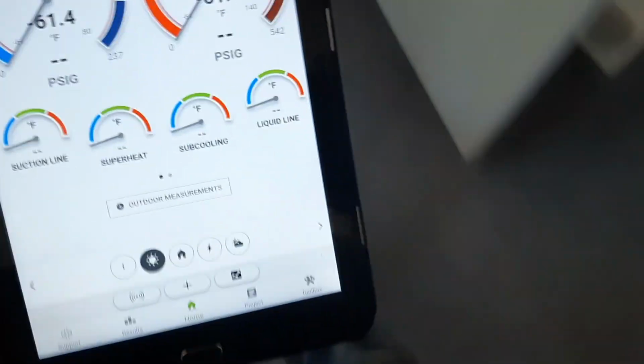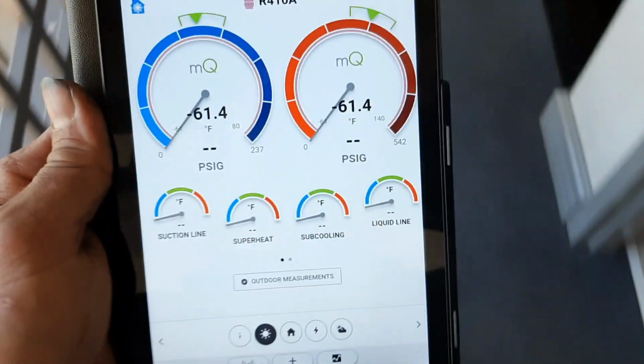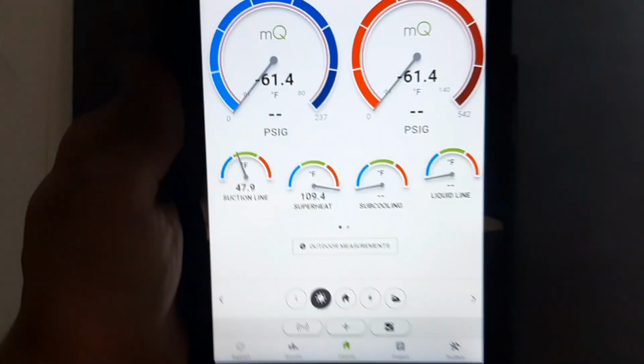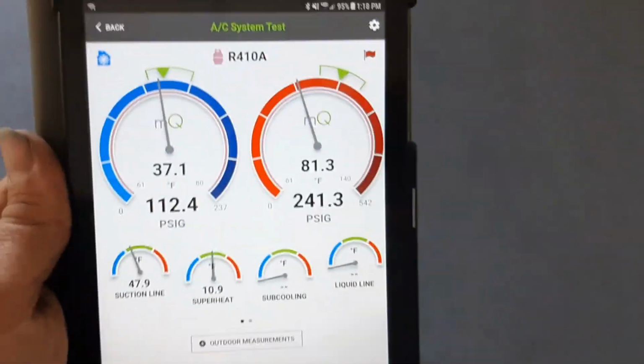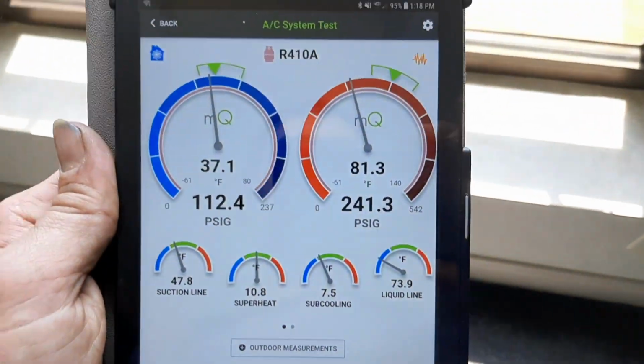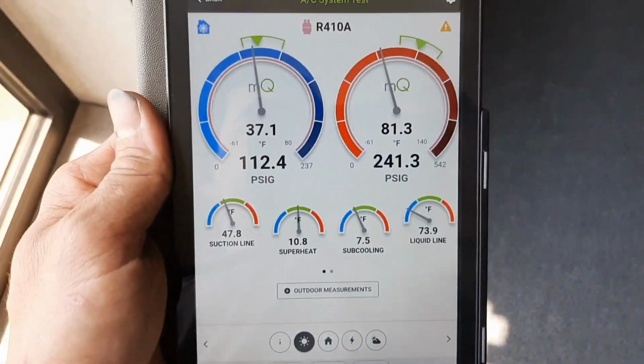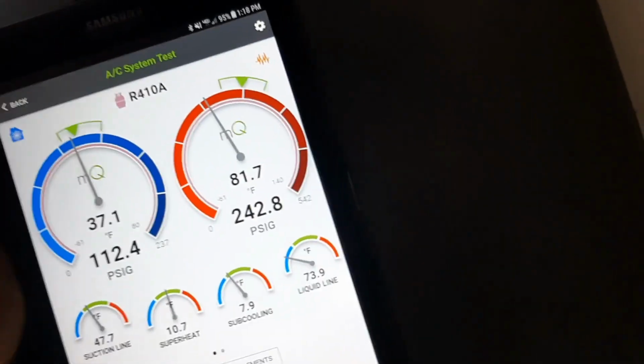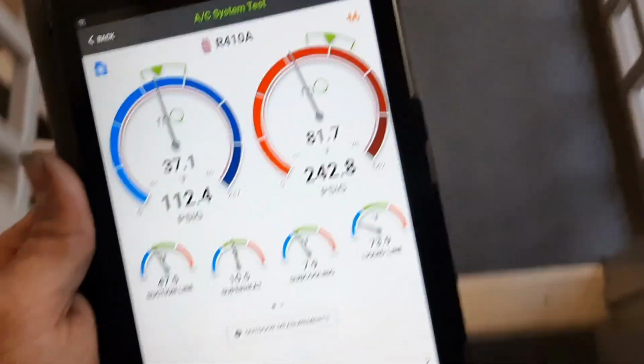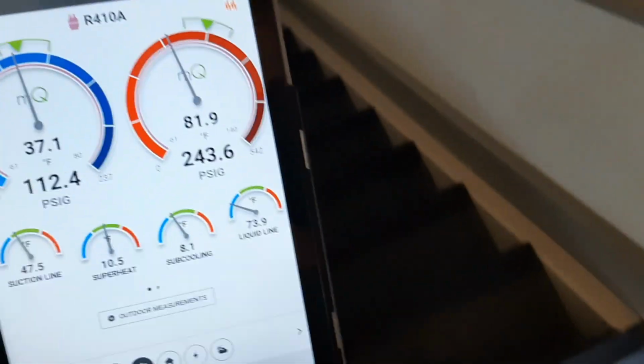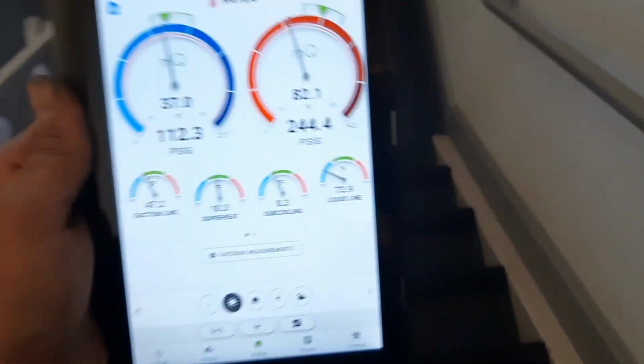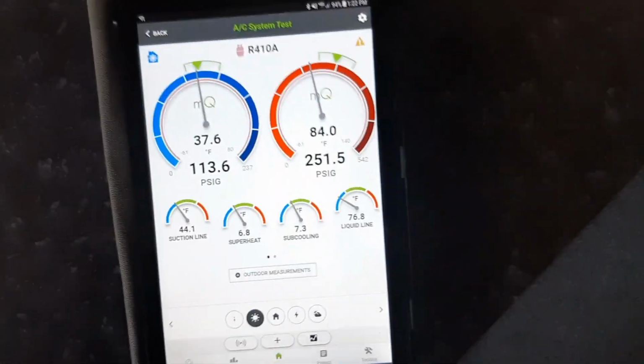It's only going to improve as that coil dries out. I'm dropping my probes now. There we go. So we'll let it run for a little while. We're dropping temp. It's about 75 in the space right now. This does have outside air as well. So we're probably gonna make sure that's open, because we've got airflow issues. But you know, my coil at 37 degrees, everything's within range. It's all looking reasonable. So it's all looking about the same.